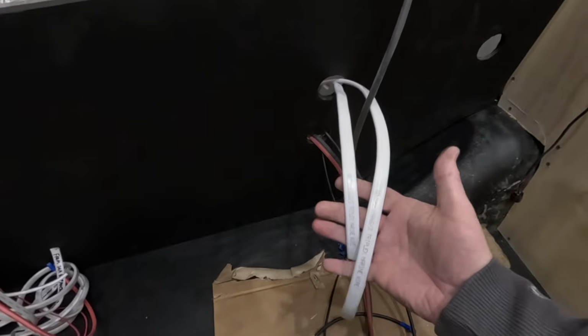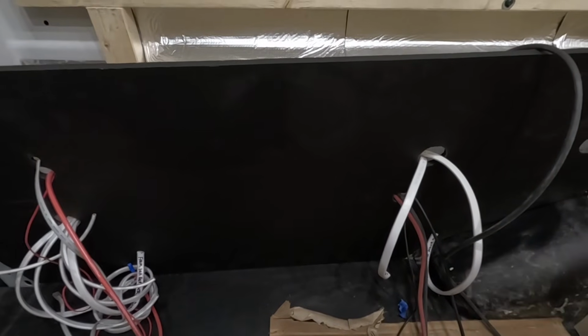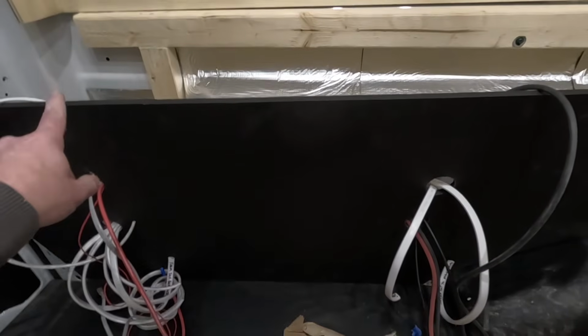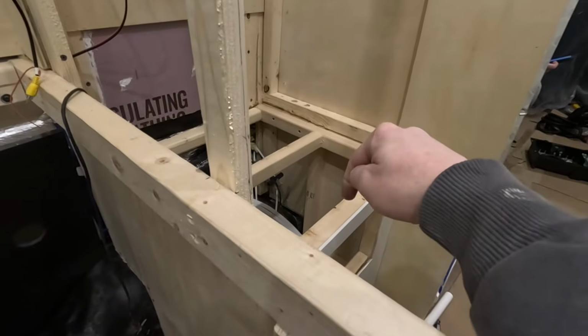This is inverter in, inverter out. But like I said, I'm putting a manual switch, so basically if the inverter were to ever fail, it's just a fail-safe. If the inverter were to ever not work, or we want to bypass the inverter on shore power, you can just switch it to where it will not run through the inverter. The shore power will come directly in and then go to the panel over here.